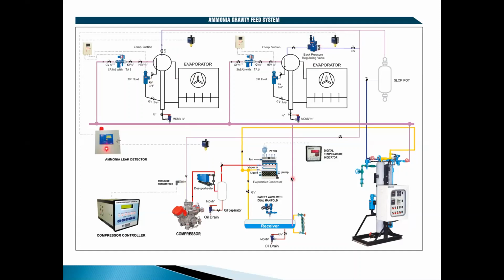This schematic typically shows how the liquid travels from the receiver, goes through the expansion valve into the accumulator and then to the evaporator. The return from the evaporator comes into this accumulator, which we also call a liquid separator. The liquid falls down and the gas goes to the compressor. The compressor compresses the gas and raises its pressure so that it can get condensed in the condenser. The schematic shows different controls and applications. We'll see more controls in detail.